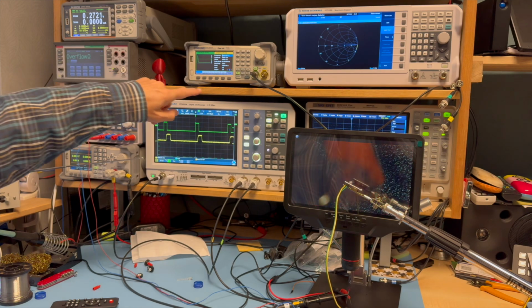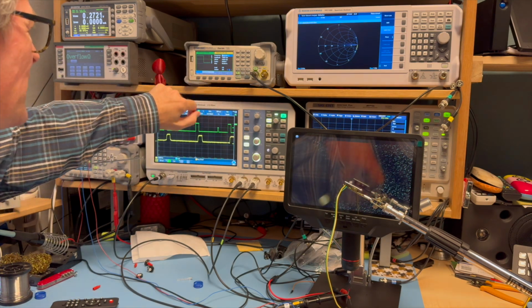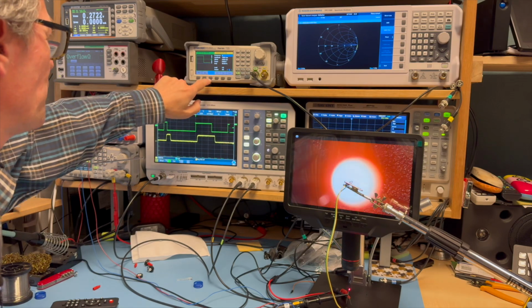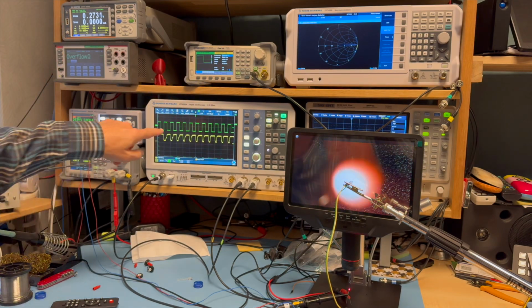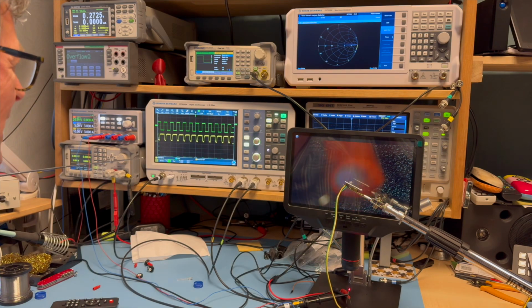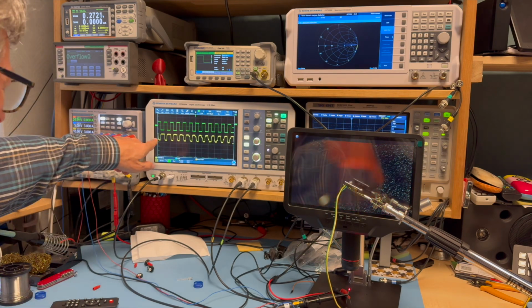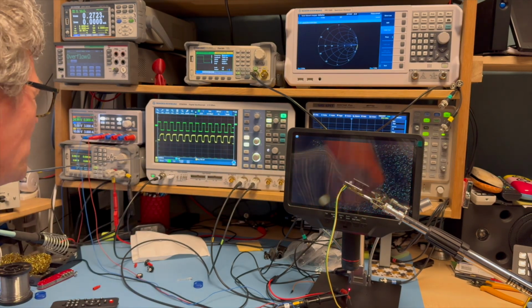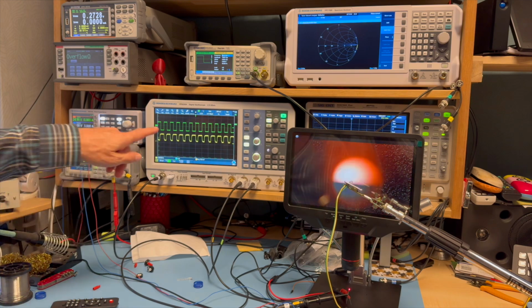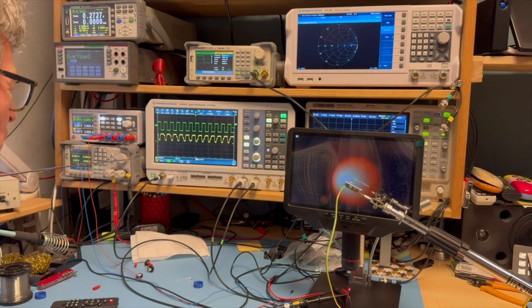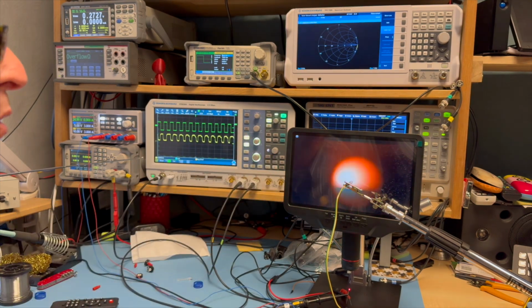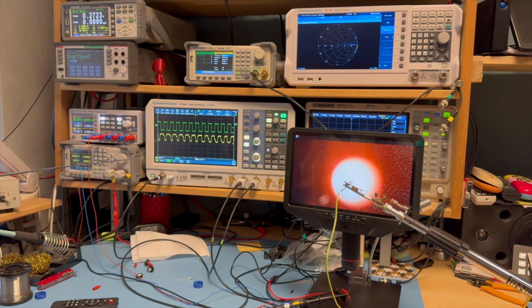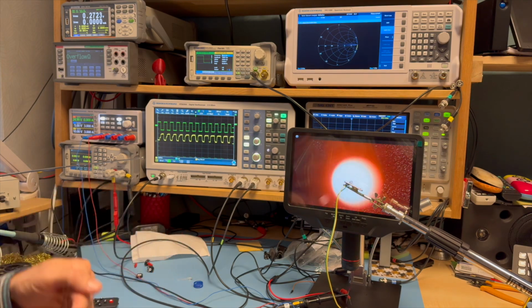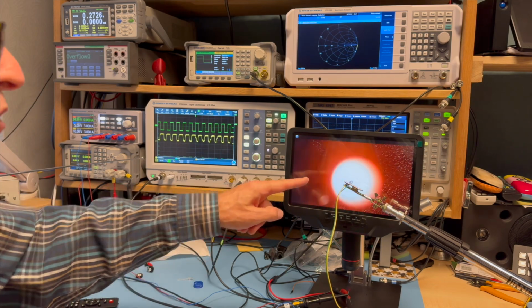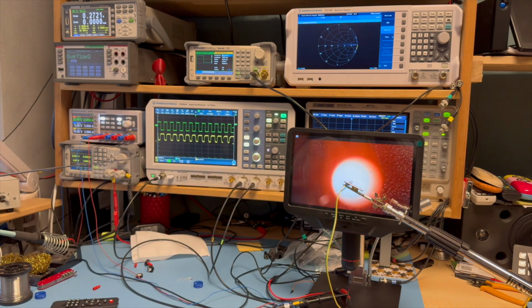In order to do that, I'll go to a more basic square wave. I'll take a square wave with a 50% duty cycle, and let me take a signal of 5 Hz. So 5 times a second the LED is going on and off. And then I'm going to examine again what we're getting back from the screen, and that looks perfectly fine as well. It can follow every flash of the LED. So that means that the screen is refreshing now. At least it's showing us a refresh at least 10 times a second, because we must see an on cycle and an off cycle of the LED. So we are successfully displaying at least 10 updates a second from here.